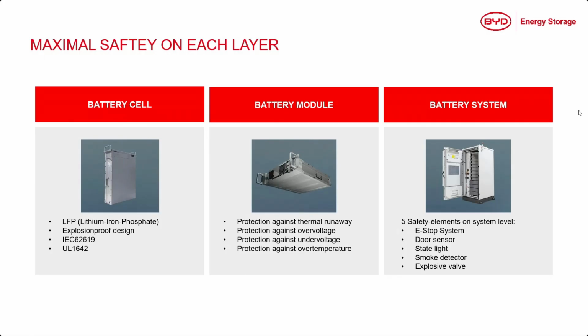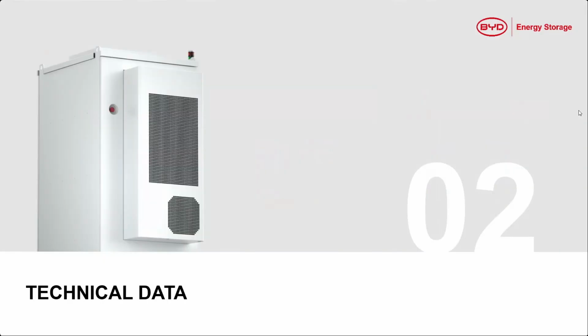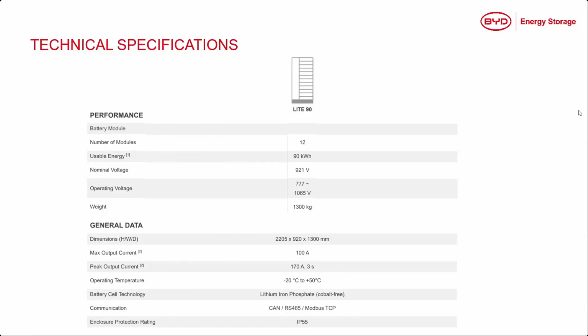At the system level, on the cabinet, we also have standard safety measures like an e-stop system where you can push a button or receive a signal from outside, a door sensor, a status light, a smoke detector, and an explosion valve required by UL. This sits on top of the unit, so if there's high pressure, it can release through the top.